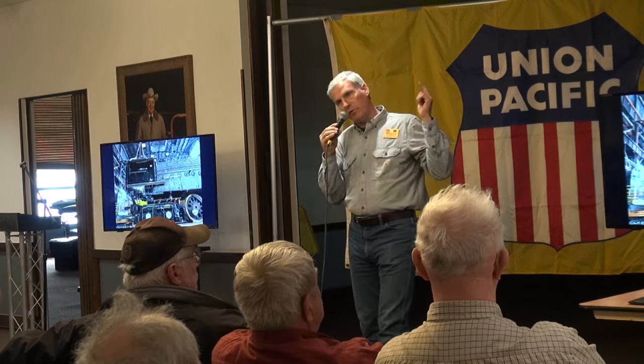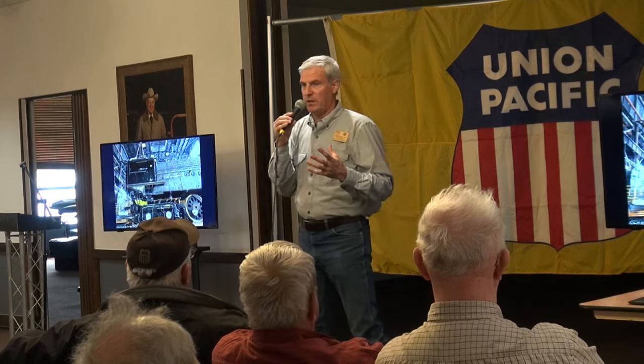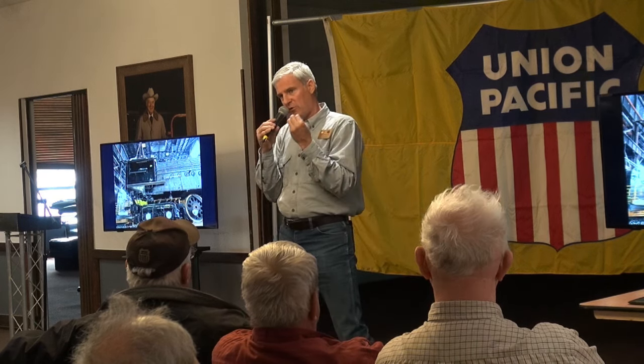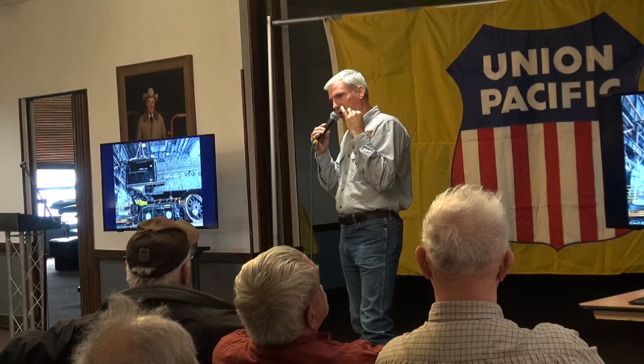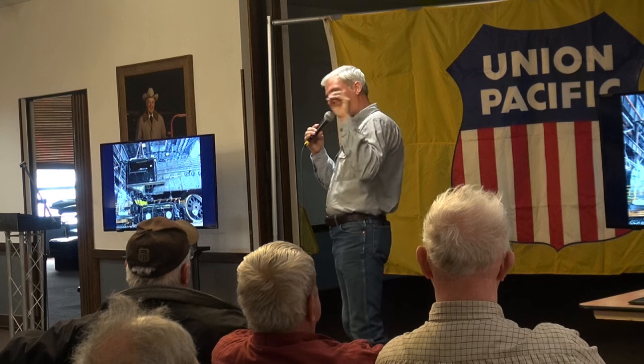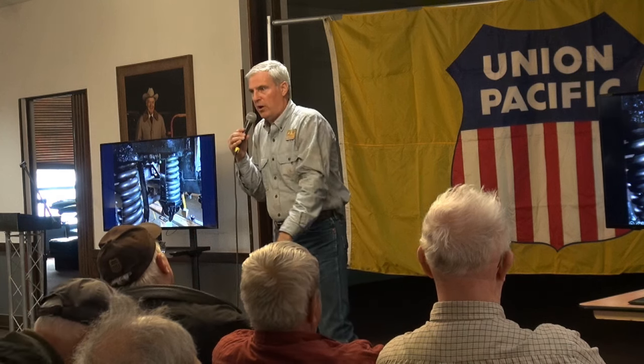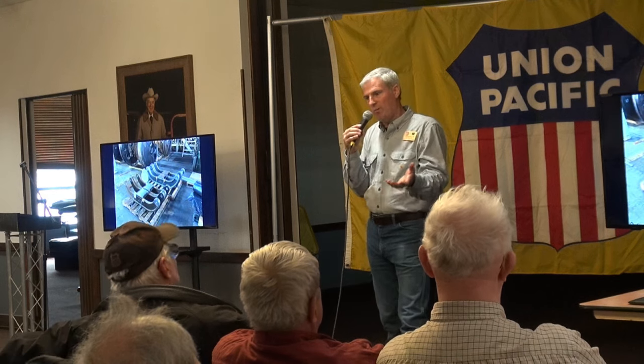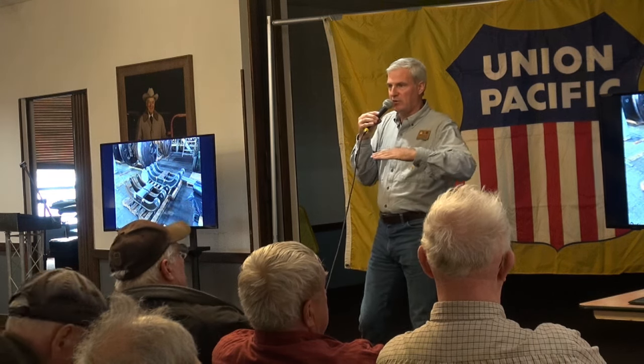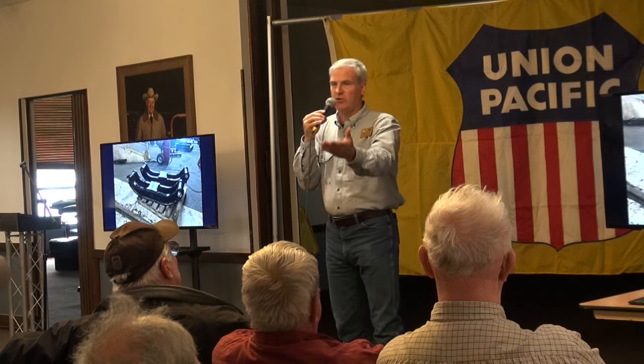Now you pump your water through it. And that water goes through, and all the calcium in that water has a strong attraction, and it's going to take the place of that sodium. Now the calcium is going to get sucked out of the water. You like my sound effects? Yes. But the sodium is released into the water. So now you get sodium carbonate, sodium bicarbonate, and that's what drives that pH up, and that's why we blow down so much. So to answer your question, yes.